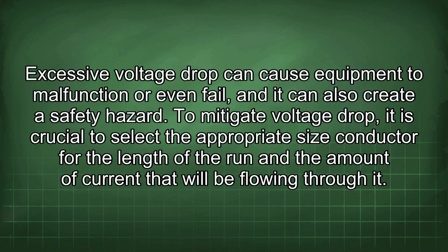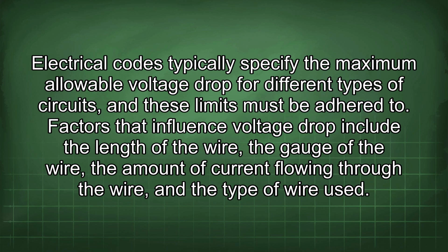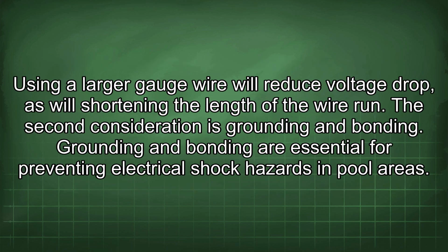To mitigate voltage drop, it is crucial to select the appropriate size conductor for the length of the run and the amount of current that will be flowing through it. Electrical codes typically specify the maximum allowable voltage drop for different types of circuits, and these limits must be adhered to. Factors that influence voltage drop include the length of the wire, the gauge of the wire, the amount of current flowing through the wire, and the type of wire used. Using a larger gauge wire will reduce voltage drop, as will shortening the length of the wire run.